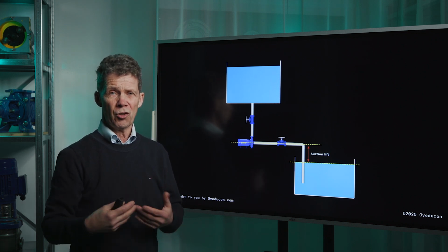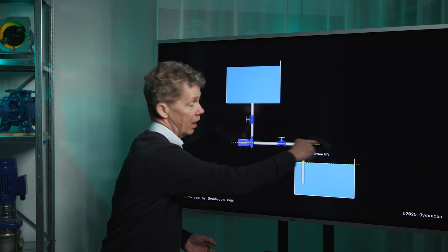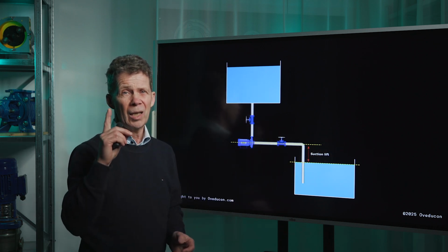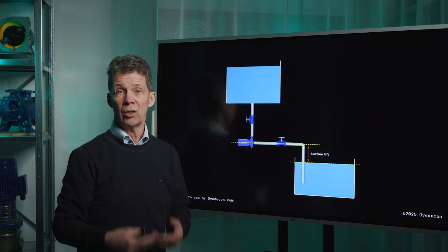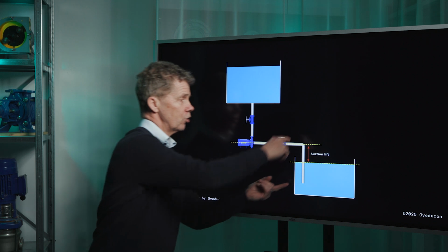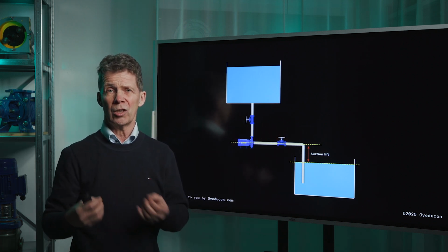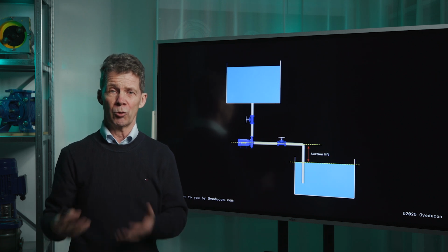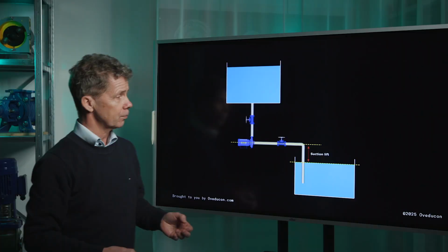And to determine the suction lift, you take the height of the eye of the impeller and be aware, take the lowest medium level possible in your suction tank. And the difference between those two levels, that height, that is the value you have to take for your suction lift. The other possibility is that you can find it in a technical drawing.